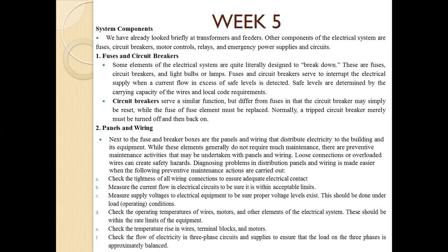Check the operating temperatures of wires, motors, and other elements of electrical system. This should be within the rated limits of the equipment. Okay? Yan ginagawa natin yan sa preventive maintenance. Check the temperature rise in wires, terminal blocks, and motors. Check the flow of electricity in three-phase circuits and supplies to ensure that the load on the three-phase is approximately balanced.